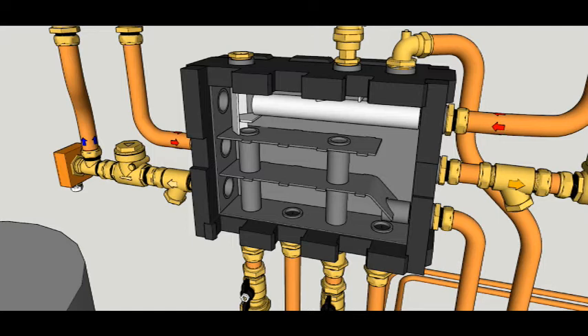In the flow chamber at the top, you'll see pipe arriving at the right hand side brings any water that comes into that port right across to the left hand side of the flow chamber, where it turns back on itself and all the water then will flow from left to right across the flow chamber at the top. So if a boiler is connected to the top left hand connection it would flow from left to right, but also if a boiler is connected to the right hand connection it'll pass through that pipe we just spoke about and then flows in the same direction from left to right across the flow chamber.